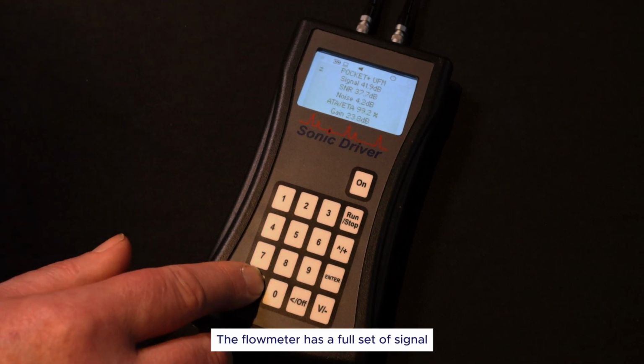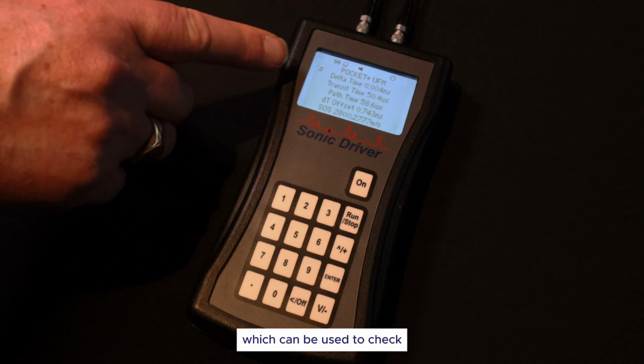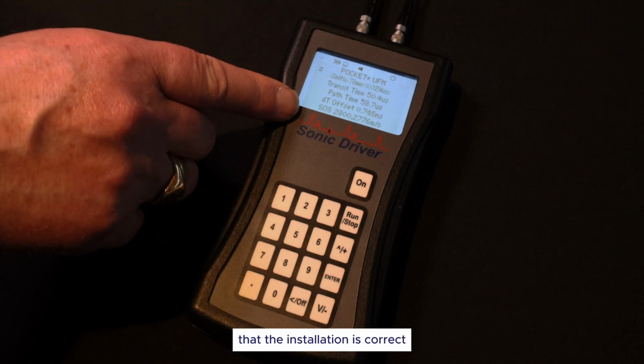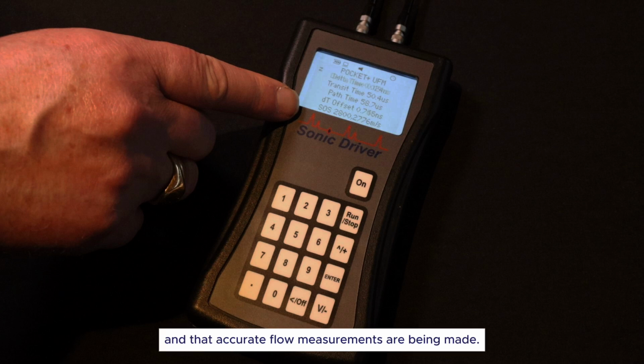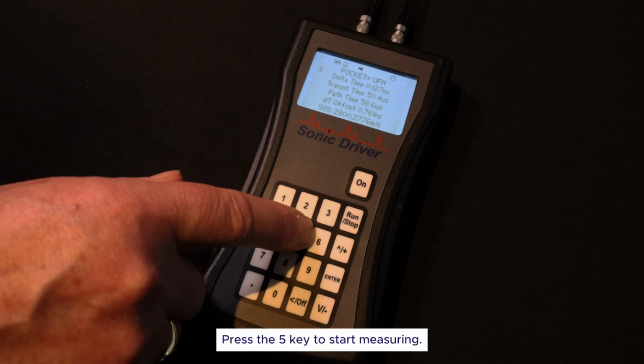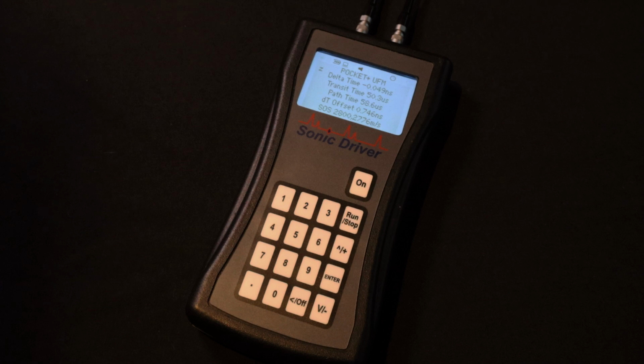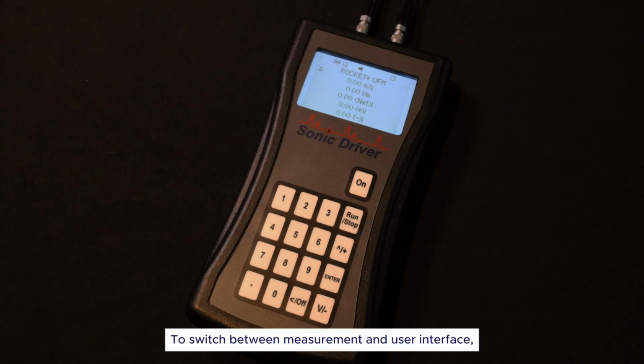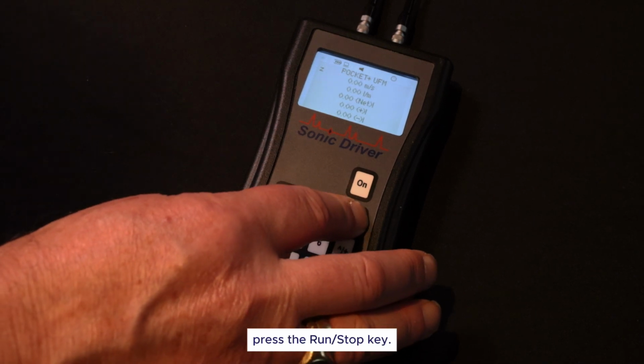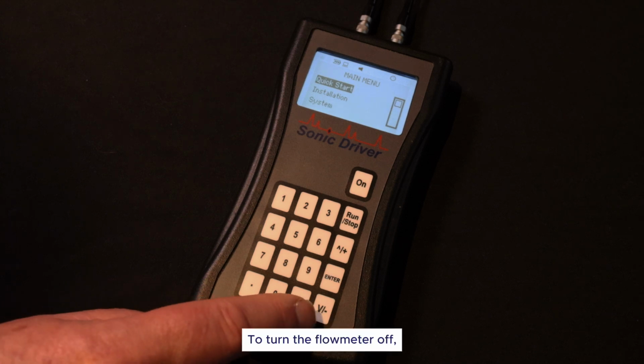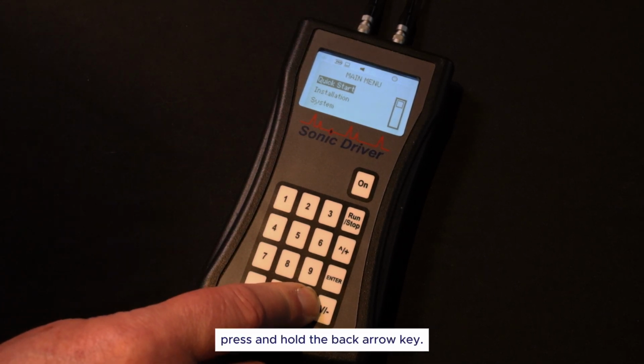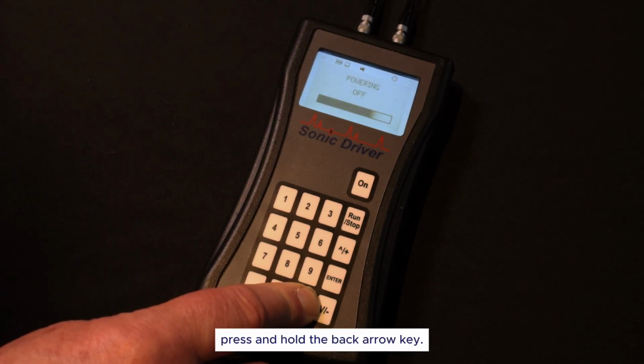The flow meter has a full set of signal and time diagnostic values, which can be used to check that the installation is correct and that accurate flow measurements are being made. Press the 5 key to start measuring. To switch between measurement and user interface, press the Run Stop key. To turn the flow meter off, press and hold the back arrow key.